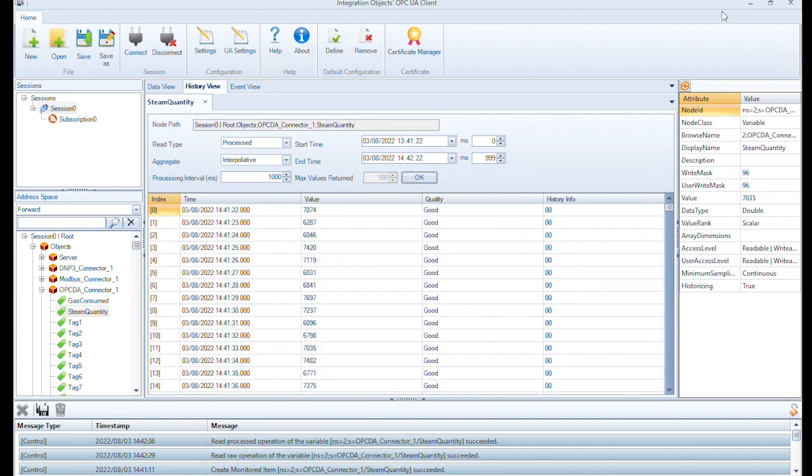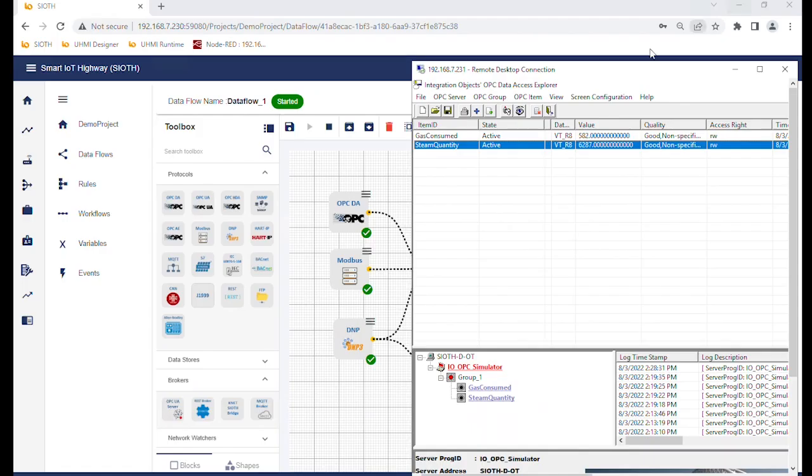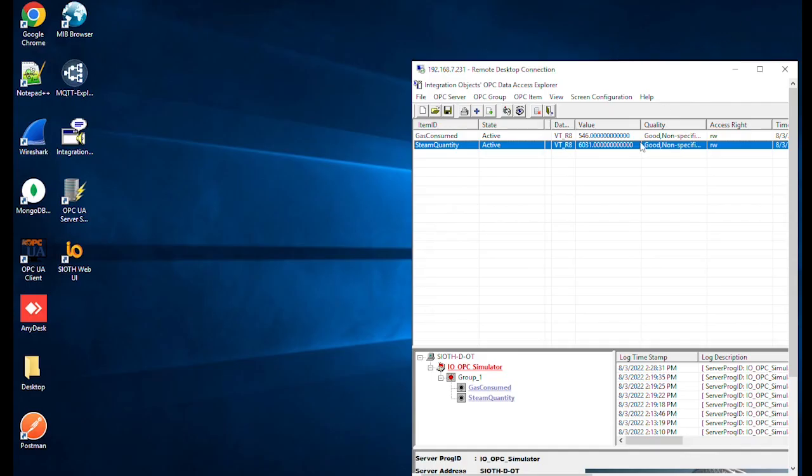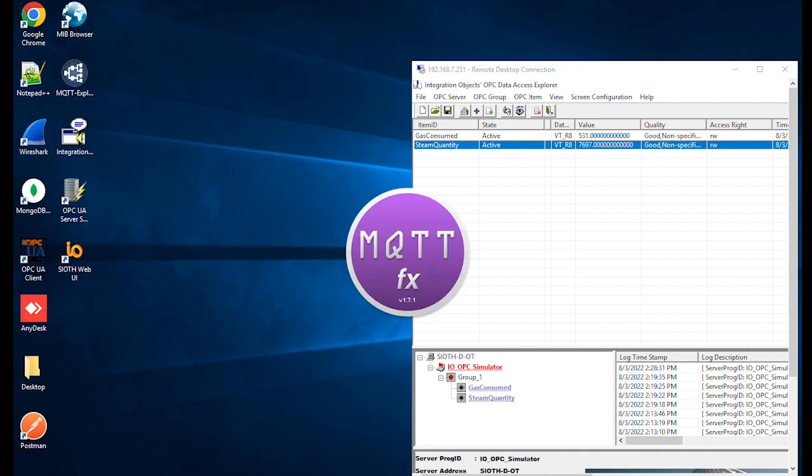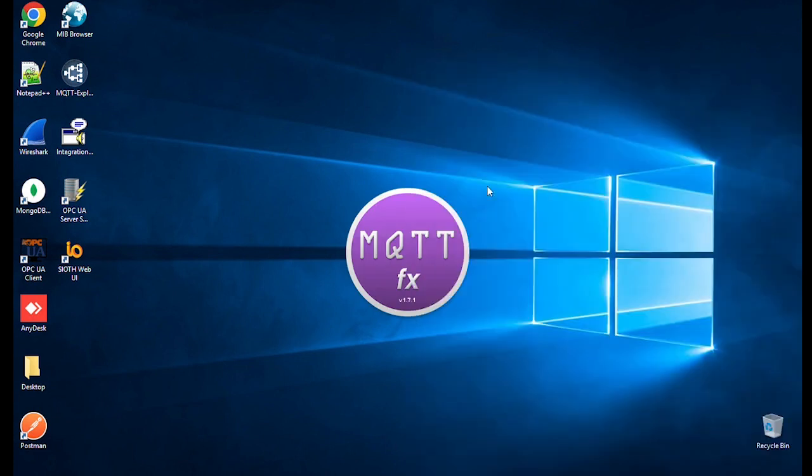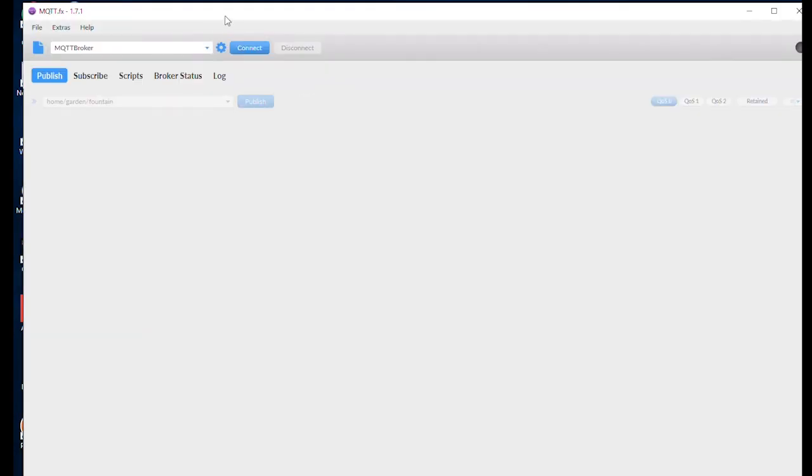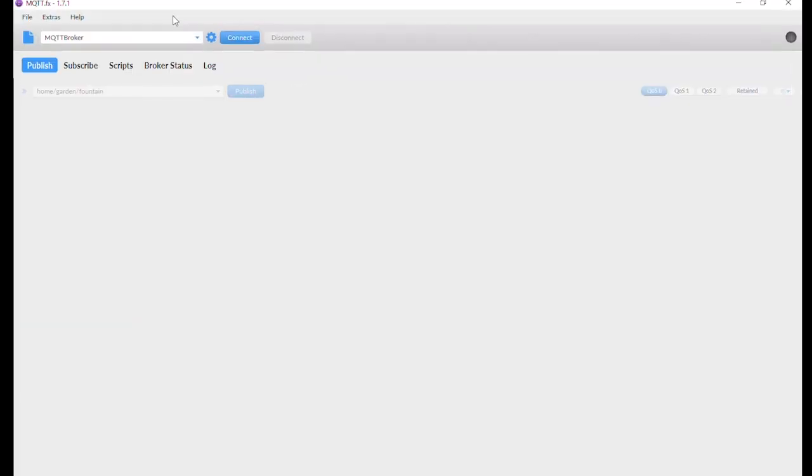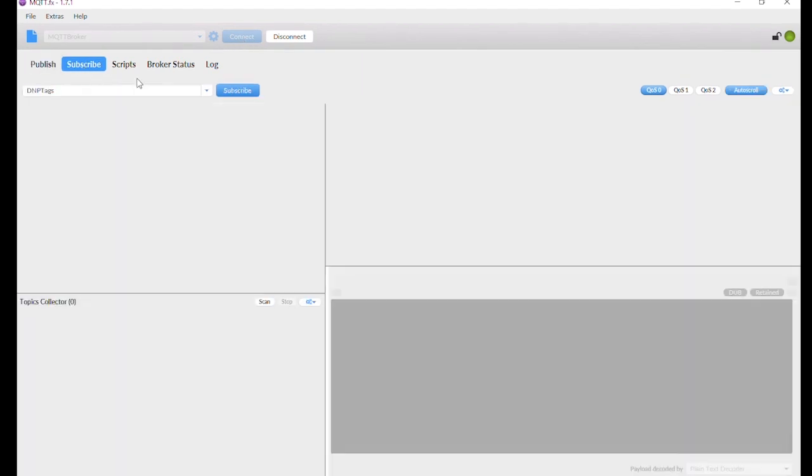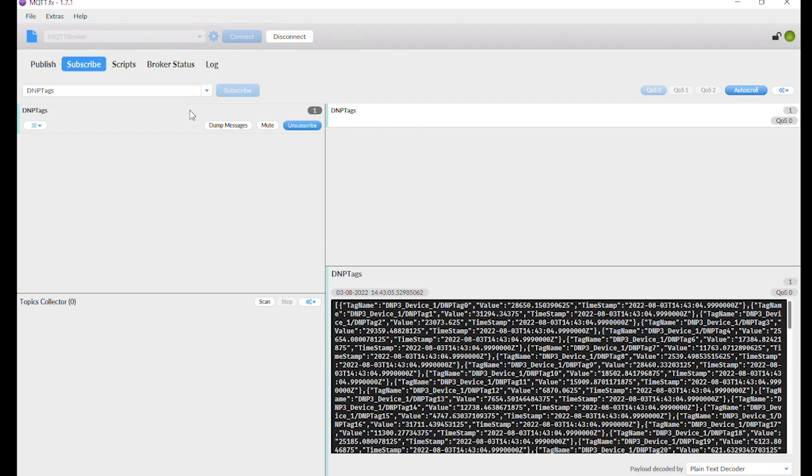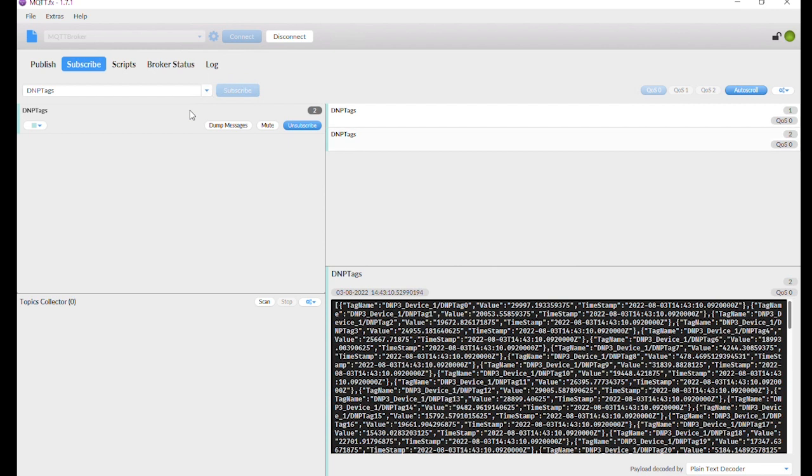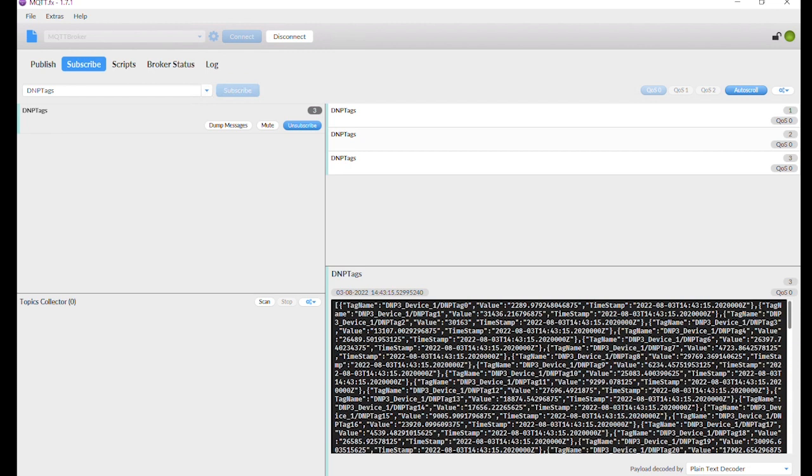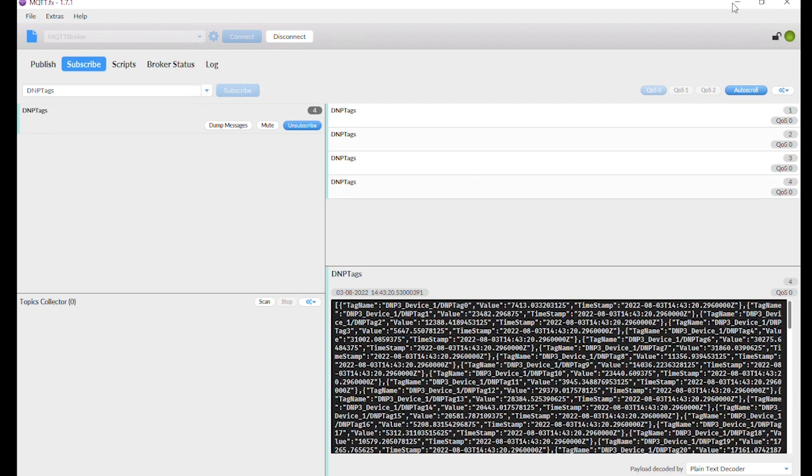Let's check that the DNP tags are also published to the SIOT MQTT broker. To do so, we will use the MQTT FX client. Connect to the SIOT MQTT broker and then subscribe to the topic configured previously in the MQTT connector. As you can see, a new message is published to the MQTT broker on the DNP tags topic every five seconds.